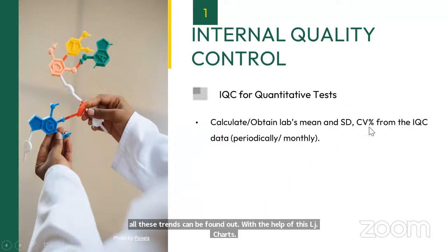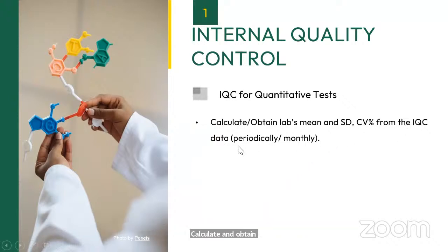Calculate and obtain the lab mean, SD and CV percentage from the IQC data periodically or monthly. So again, this question somebody raised two to three days back, whether hematology analyzers require calculating the lab mean. As I have mentioned, it is not required for hematology because your lot changes every month or maybe every 15 days. But as far as biochemistry is concerned, your lot will remain constant even for 6 months and even for 9 months. In 1 year also it remains the same. So you need to calculate the lab mean. You have to use lab mean and SD. You should calculate the CV percentage from the data periodically. How periodically? Monthly, 2 monthly, 3 monthly, quarterly, 6 monthly, as per the guidelines which are available.